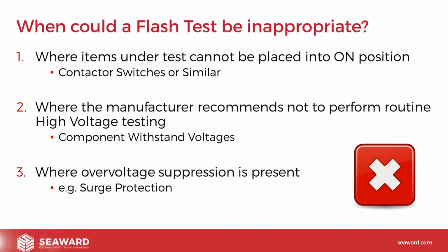And therefore, what will happen is we'll actually initiate false failures, where the device sees it as an overvoltage, effectively connects live to earth, and then our tester will see that as a short and fail the product. It's actually not a failure, it's the device doing what it's designed to do. So these are the three instances where you may need to consider not performing a flash test, and the subsequent tests we'll talk about will offer you some additional methods of testing. It could be that you perform the flash test in conjunction with one of these, so you're doing a full and complete test on it, or you may substitute the flash test entirely for one of these tests.